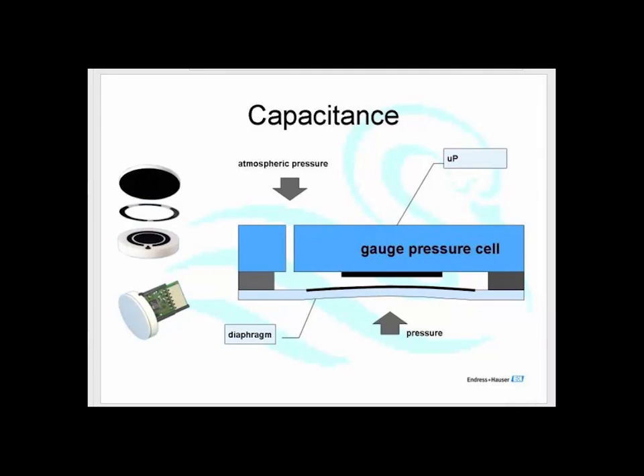In the old days, using the old metal pressure cells with wires coming out, you used to have two for every installation: one installed and one in the factory being repaired, because they would go wrong all the time. I've seen these go wrong, go out of calibration because the operator cleaned it with a hose pipe, or wiped it with a rag.